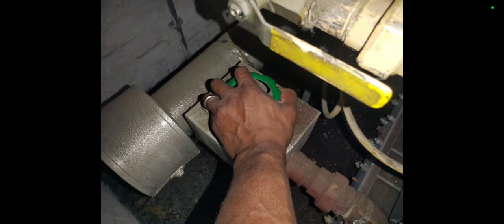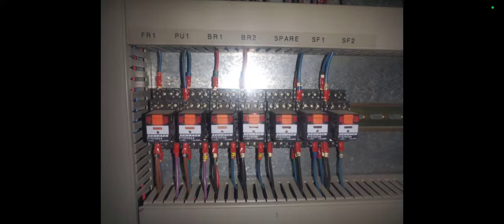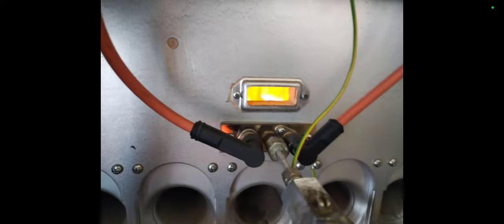You can see it. It was leaking quite a lot. So I isolated flow and return on it, but I think later on I went back to inspect it another day and the valves were letting by. The relay wasn't making. You can see it has BR1, BR2. Well, BR2 you could see wasn't making. When it initially started up, the one on the right, you can see the flame is quite orange.